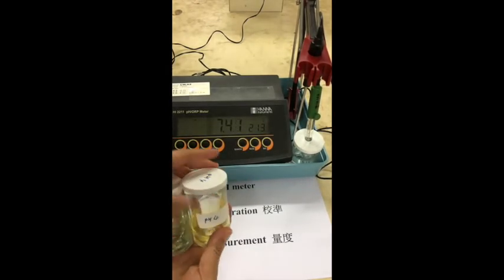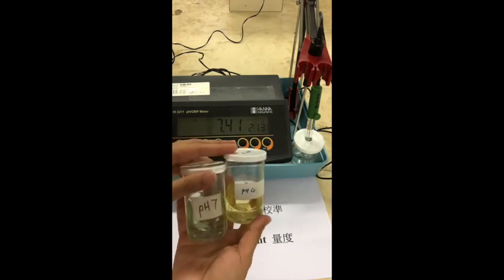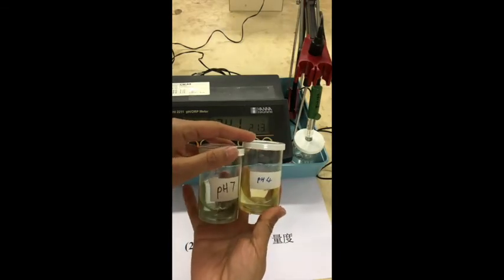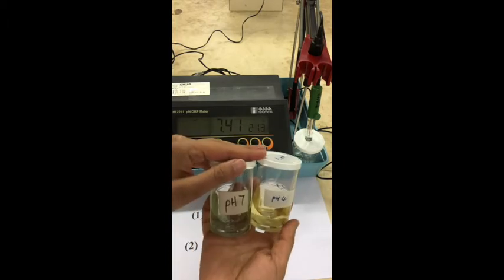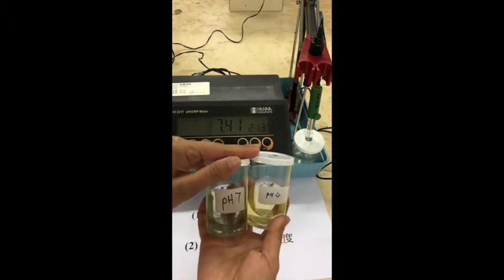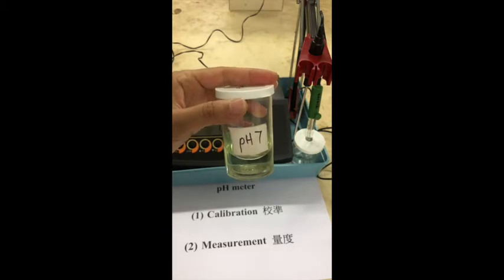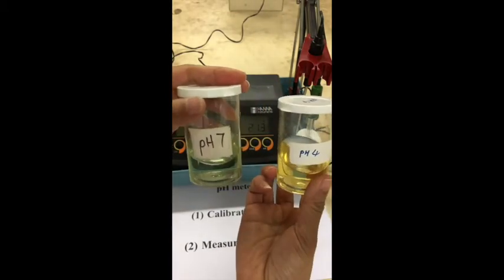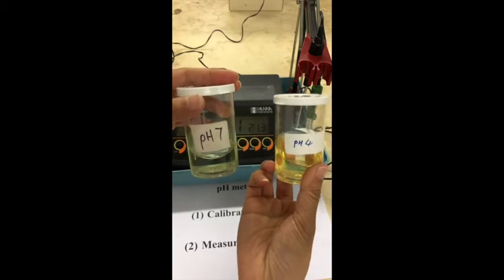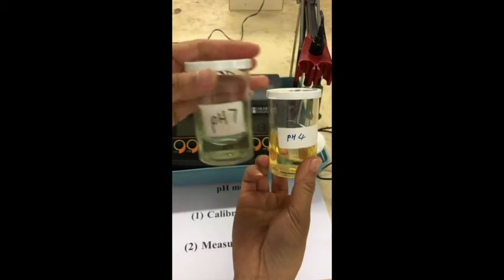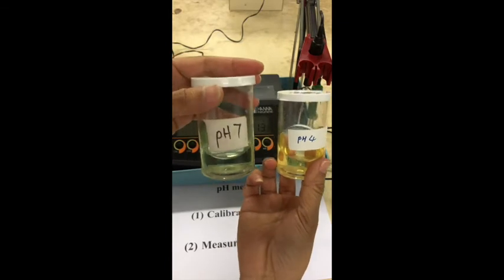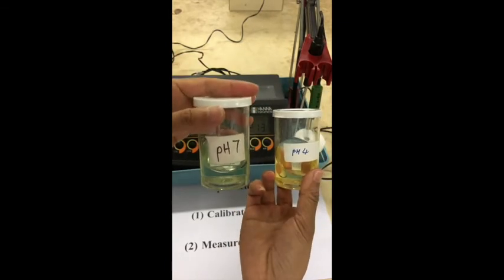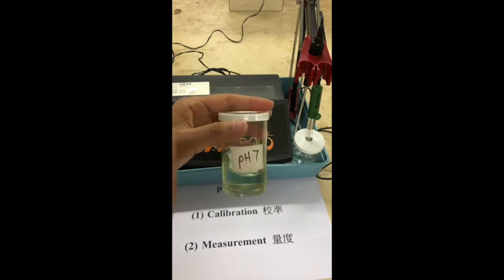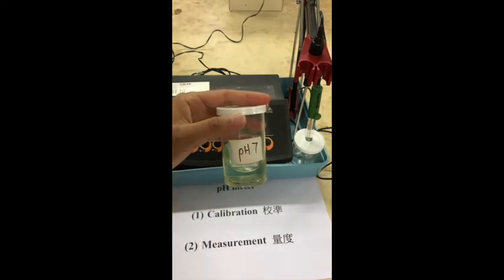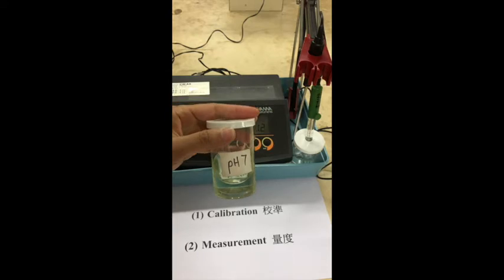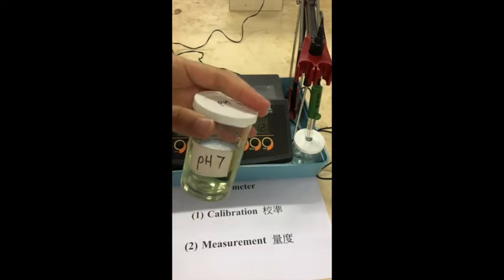For different pH meters, there will be 2-point calibration, which means using two buffer solutions, or 3-point calibration. The buffer solution with pH 7 is essential for all calibrations. If the sample is acidic in nature, we will use pH 7 and pH 4, because the pH of the sample has to be within the range of these two numbers. If the pH of the sample solution is alkaline, we will change the buffer solution to pH 7 and pH 10.